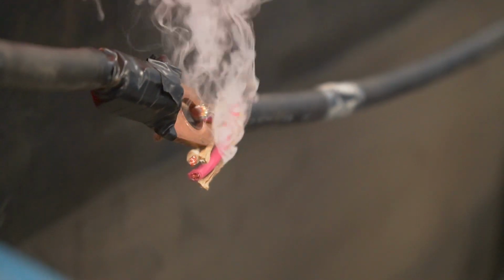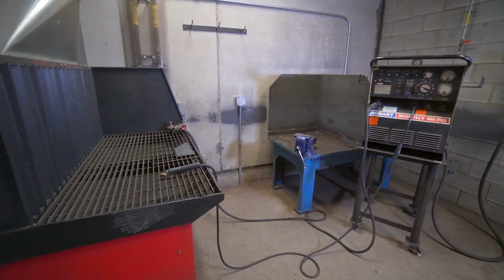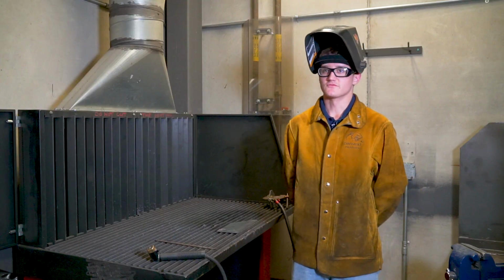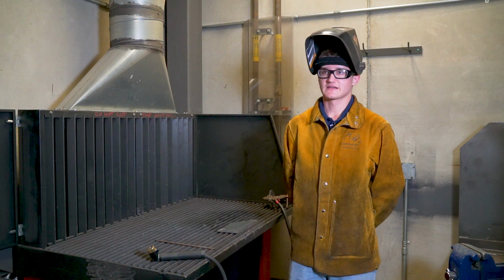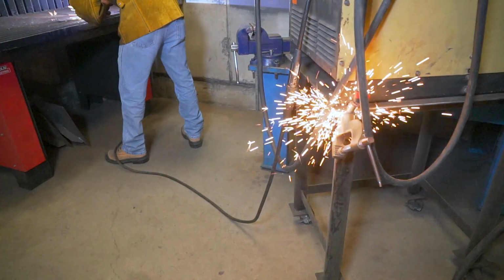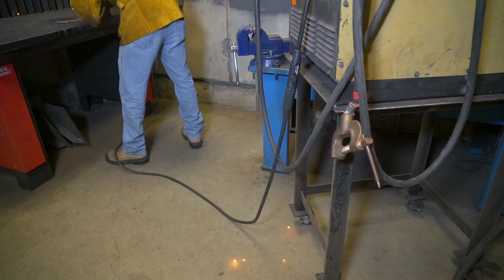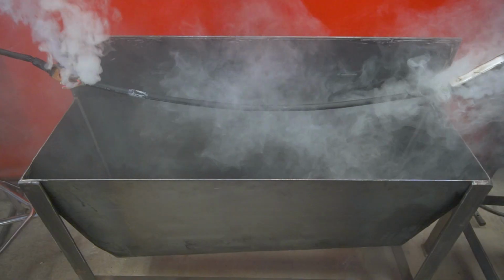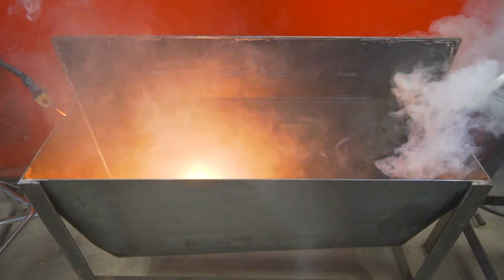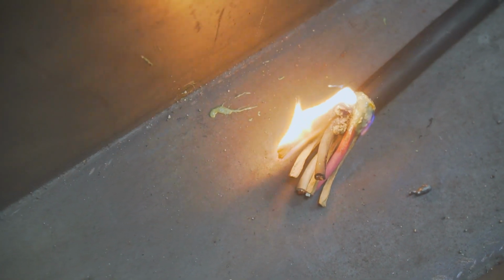Stray welding currents have led to very serious and expensive damages to equipment and electrical systems, and have been implicated as the root cause of serious industrial accidents, even resulting in death of workers. Electrical arcing in unexpected locations in a building can also start fires or explosions, since there is no way to predict where the current will find the path of least resistance through an industrial facility or construction site.